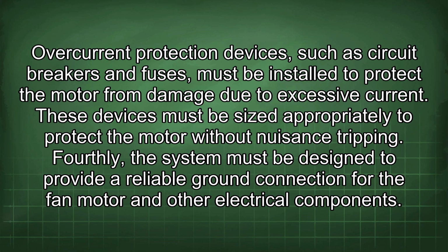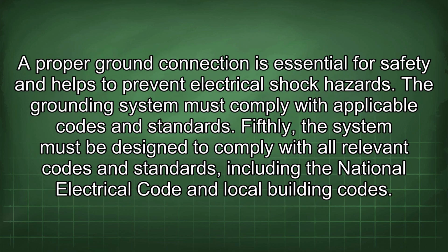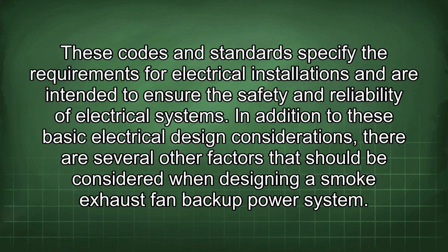Fourthly, the system must be designed to provide a reliable ground connection for the fan motor and other electrical components. A proper ground connection is essential for safety and helps to prevent electrical shock hazards. The grounding system must comply with applicable codes and standards. Fifthly, the system must be designed to comply with all relevant codes and standards, including the National Electrical Code and local building codes. These codes and standards specify the requirements for electrical installations and are intended to ensure the safety and reliability of electrical systems.